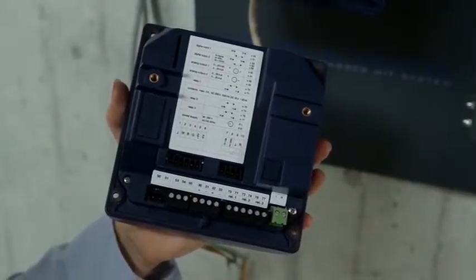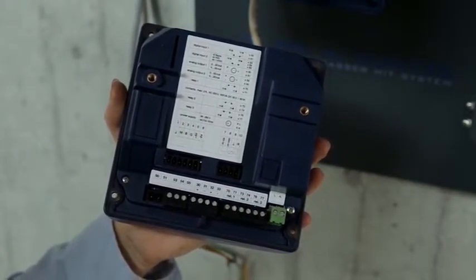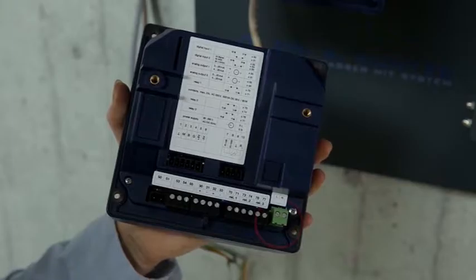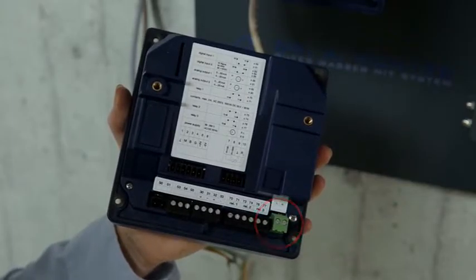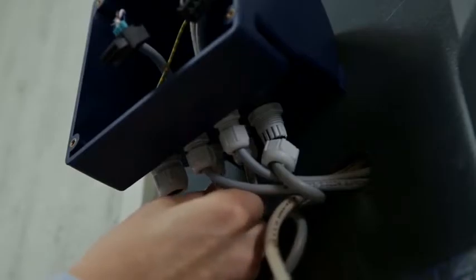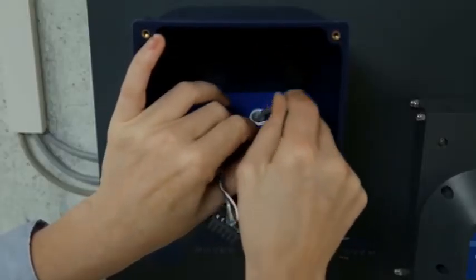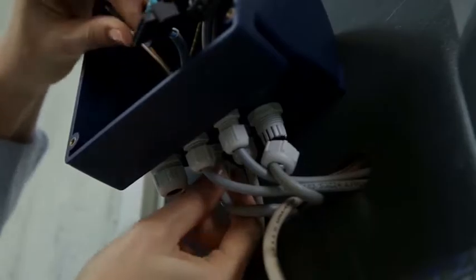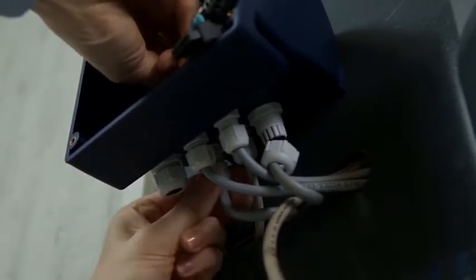The connection diagram can be found on the back of the instrument. It shows the terminals for power supply, alarm relays, 2 mA outputs and 2 digital inputs, as well as the terminals for the sensors. Pull the cables through the cable glands on the bottom of the instrument. Make sure that power is switched off during the wiring.